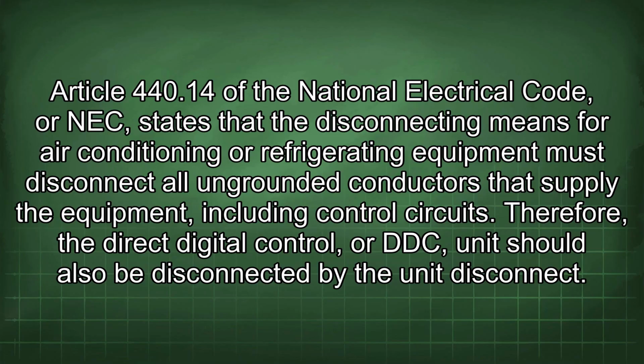Article 440.14 of the National Electrical Code (NEC) states that the disconnecting means for air conditioning or refrigerating equipment must disconnect all ungrounded conductors that supply the equipment, including control circuits. Therefore, the Direct Digital Control, or DDC, unit should also be disconnected by the unit disconnect.